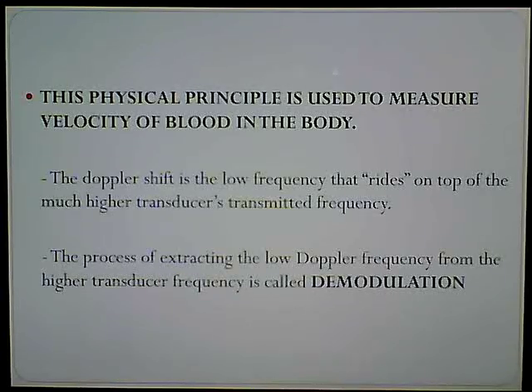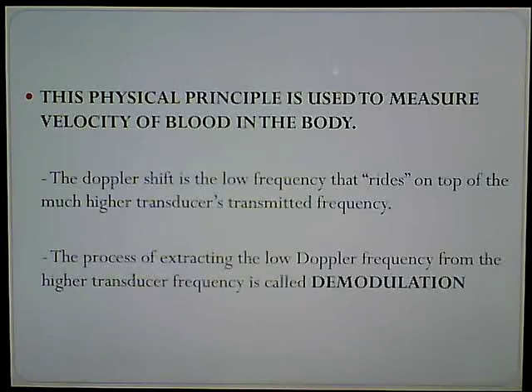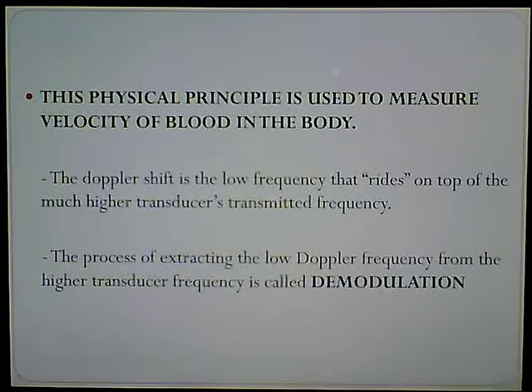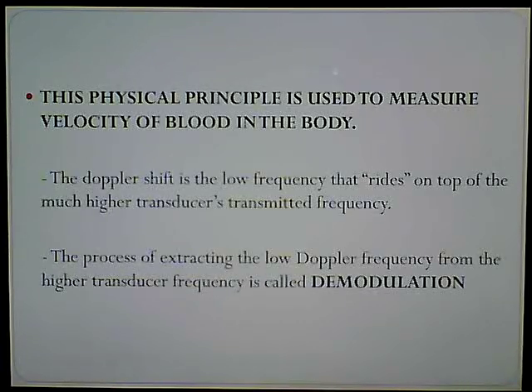It's that extra frequency that is produced when we hit moving red blood cells with our sound beam. The process of extracting the low Doppler frequency from the high transducer frequency is called demodulation — basically just skimming off the top of that extra frequency so we can process it.